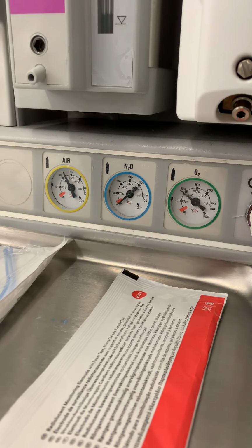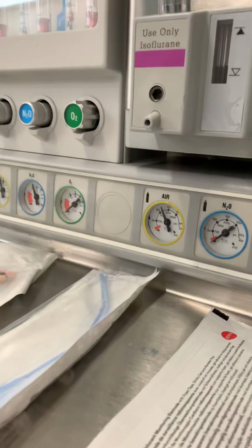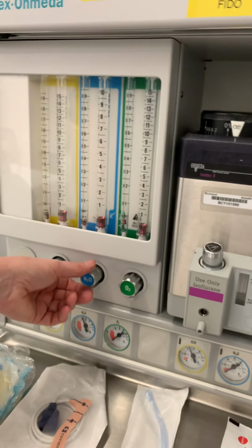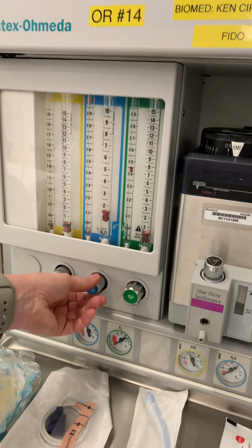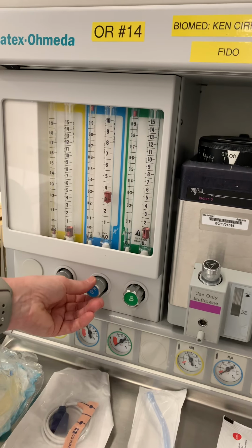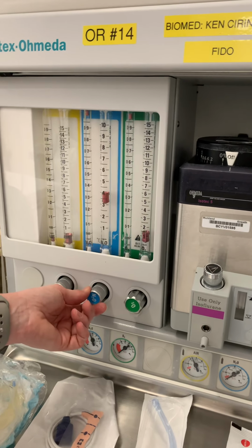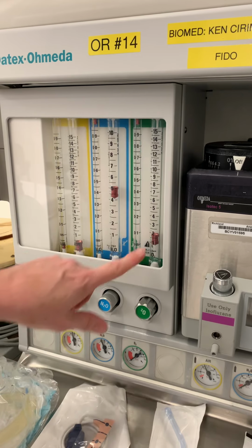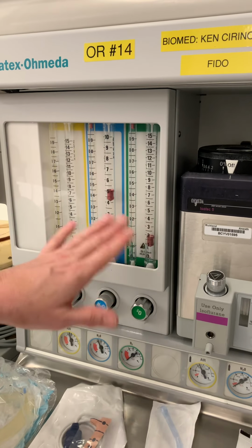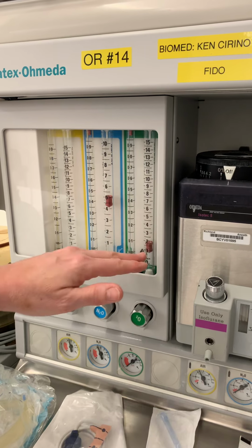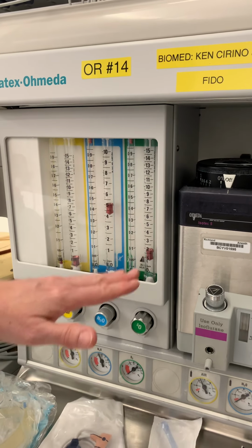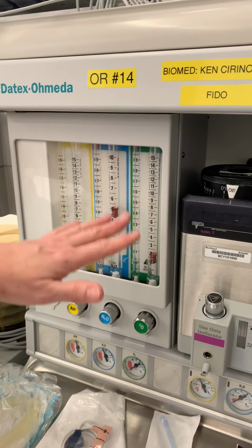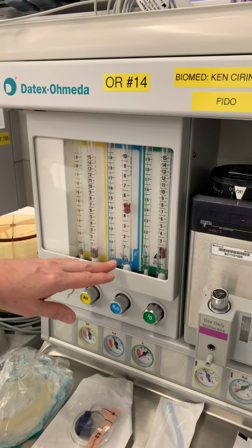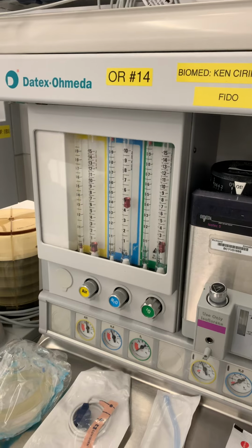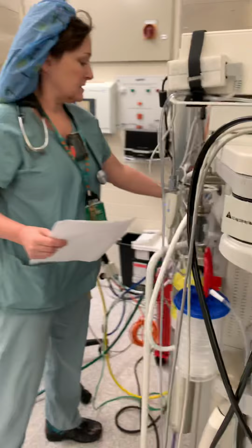Now, we also want to test our fail-safe and make sure that our proportional system is working. What this means is the machine is designed so that you cannot or should not be able to deliver a hypoxic mixture. So if you notice, if I go to turn on the nitrous, the oxygen is going to follow no matter what, so that you never deliver a hypoxic mixture. Now, if anything should happen to the oxygen supply, the nitrous should shut off, and we will see that when I go back and I turn off the oxygen cylinder.